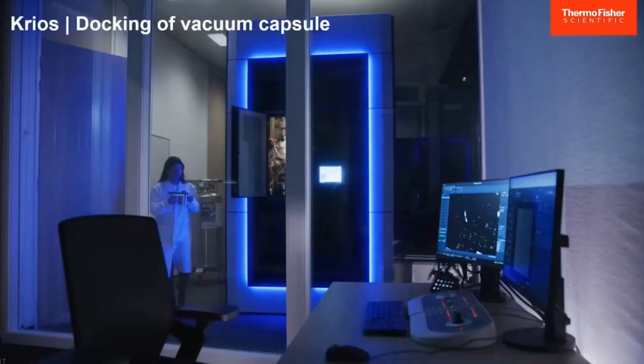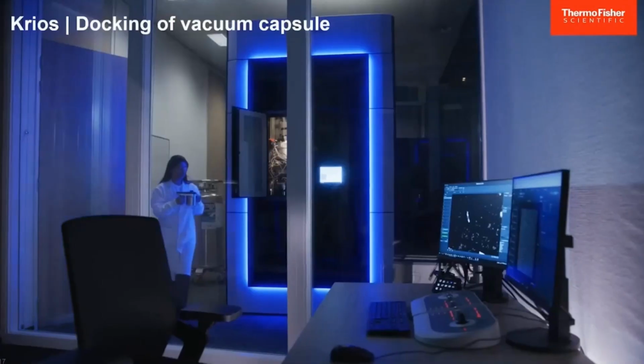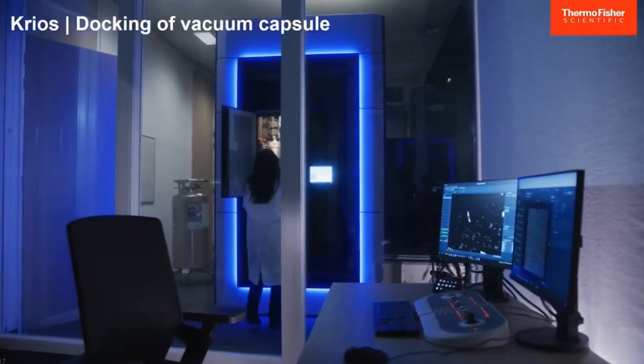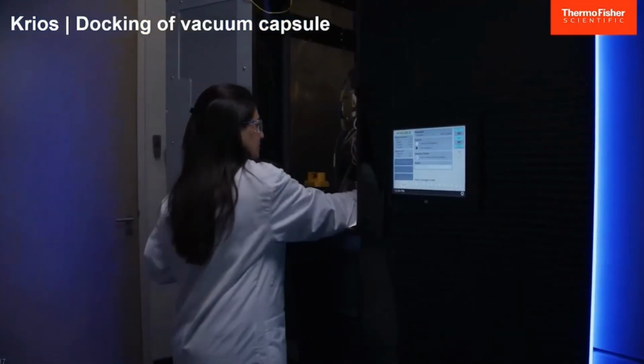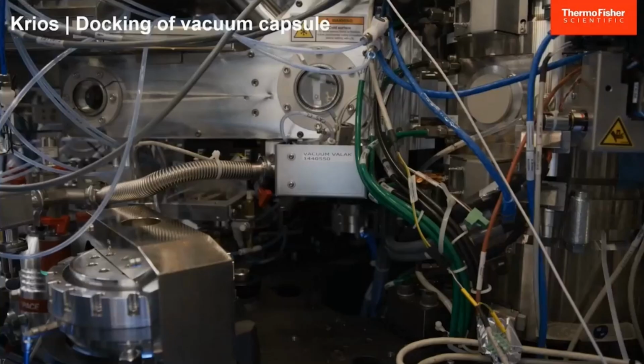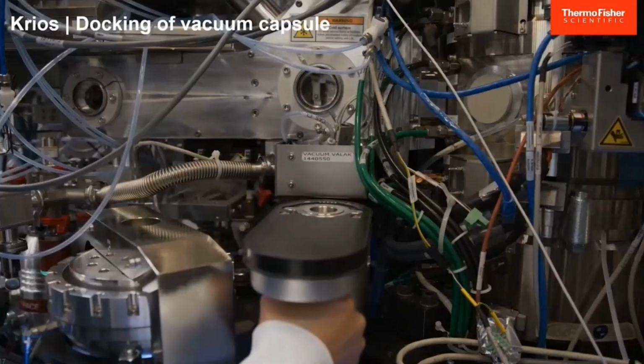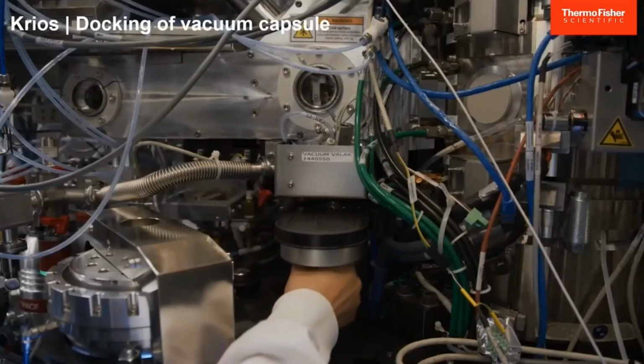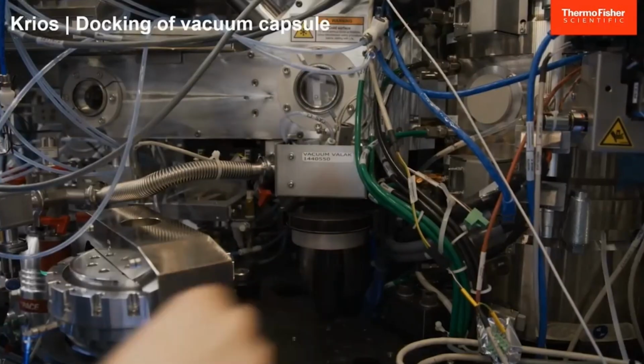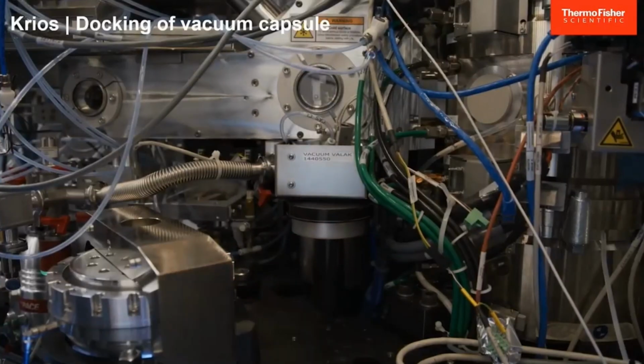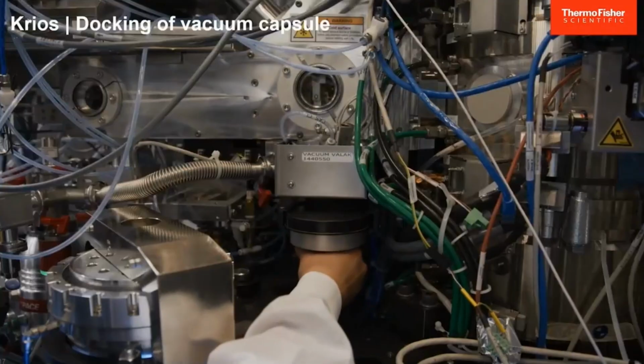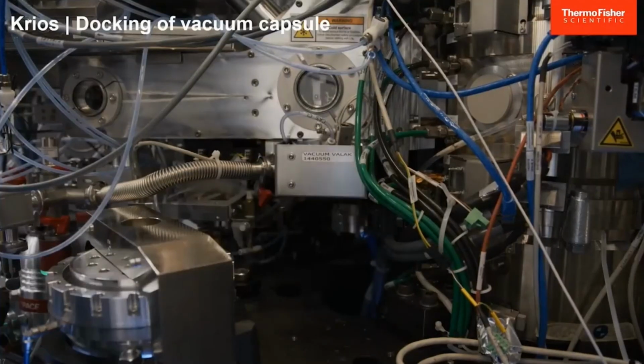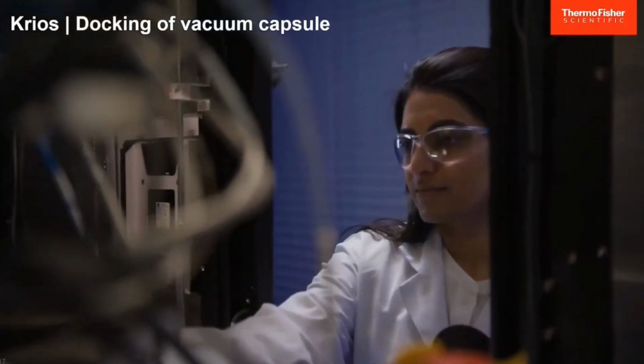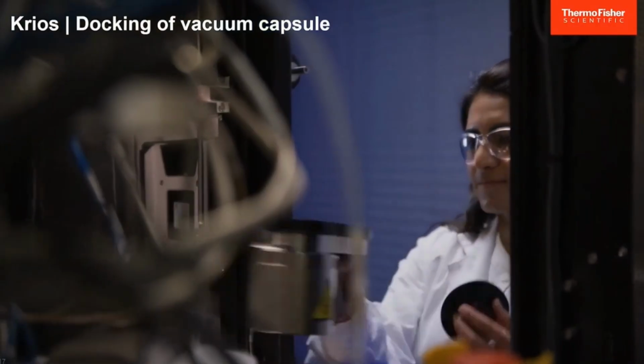you go to the Krios microscope, and under vacuum conditions, obviously, like I said, the vacuum is pumped through the autoloader, and then the vitrified samples and prepared lamella are loaded into the Krios. The cassette is uptaken with the vertical axis into the autoloader, and the grids are selected for setting up the tomography experiment.